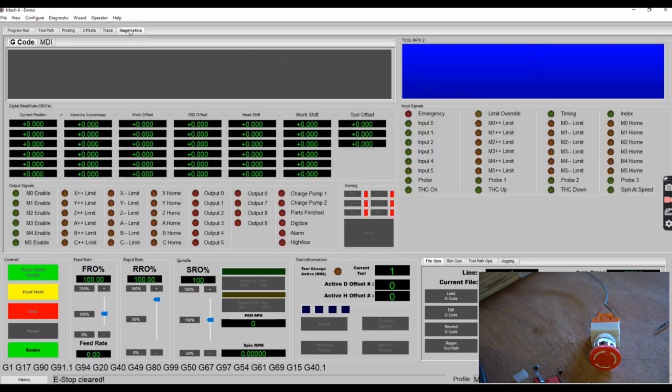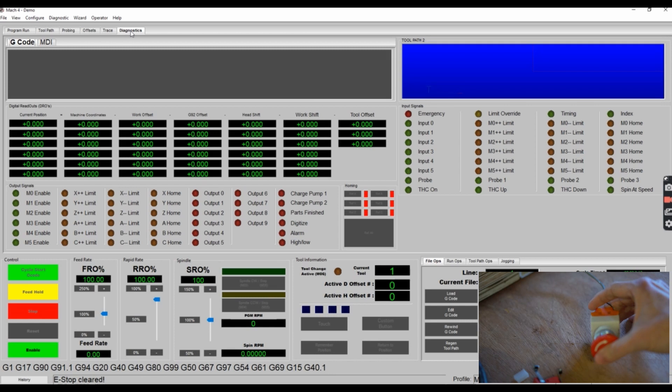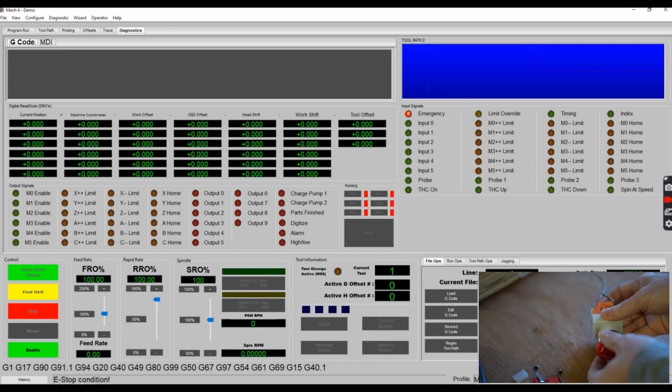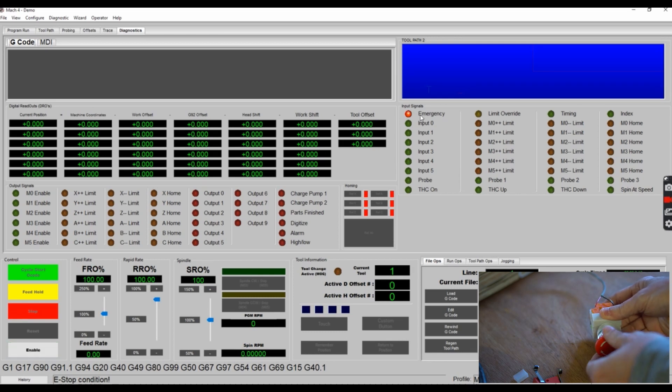You can also see the status of this e-stop button in the Diagnostics screen. So click on Diagnostics tab and in the Emergency Input Signals, you can see that light up when I engage the e-stop. And then when I release the e-stop, you can see that the light goes away.